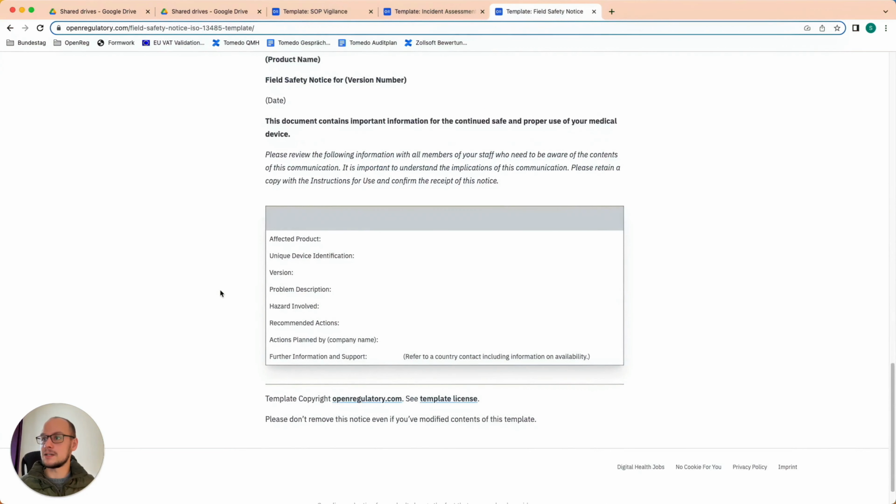The bottom part here is most important, however. Describe the workaround you suggest for users, announce a recall or a software update for your device before you perform it. Again, this is mostly industry best practice, but also auditors will be content to see that you are prepared for all eventualities. And that's it.